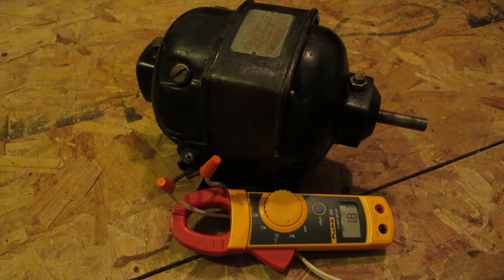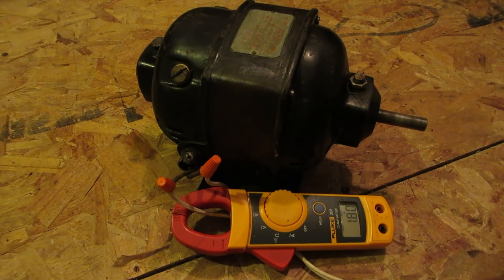It will get to a point where you will hear the centrifugal clutch activate and disengage the brushes. There's 48. 50. There we go. The brushes on this don't actually physically disengage, but they electrically will. So that's now considered an induction motor. It actually disengaged the brushes at 52 volts.